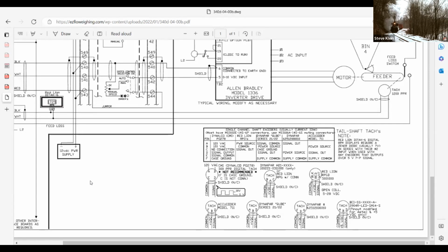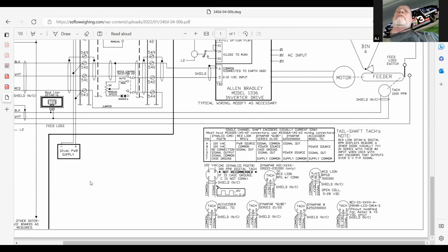Put your indicator over one of the shield sections, and note that normally the shields on the wires, your signal wires, try to sink the high voltage signal if they're running parallel so it doesn't pick up a stray signal. Try to sink it to an earth ground. Most of the time those wires are only connected on one end. They'll pass through the plugs as a separate pin. In the center you can see terminal 549 is connected on both sides, and it's also connected to common, in other words sinking at number 6 on that 1336 drive, that inverter drive. But you have to watch out that the length of cable quite often only gets shielded and tied in on one end, otherwise you'll cause yourself problems when you go to track stuff down.